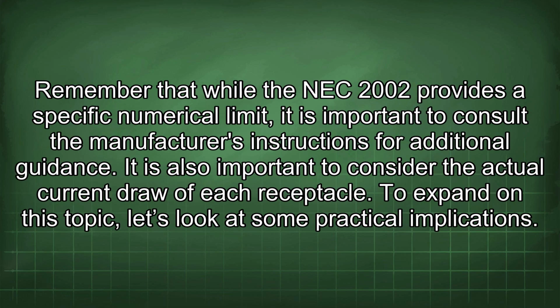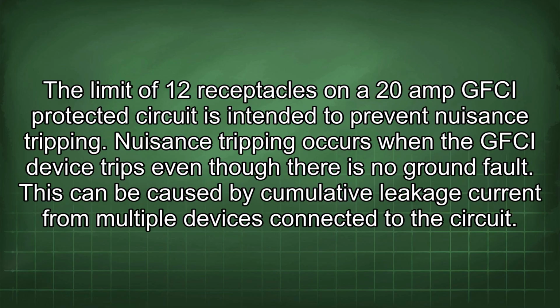Remember that while the NEC 2002 provides a specific numerical limit, it is important to consult the manufacturer's instructions for additional guidance. It is also important to consider the actual current draw of each receptacle. To expand on this topic, let's look at some practical implications. The limit of 12 receptacles on a 20 amp GFCI protected circuit is intended to prevent nuisance tripping. Nuisance tripping occurs when the GFCI device trips even though there is no ground fault.